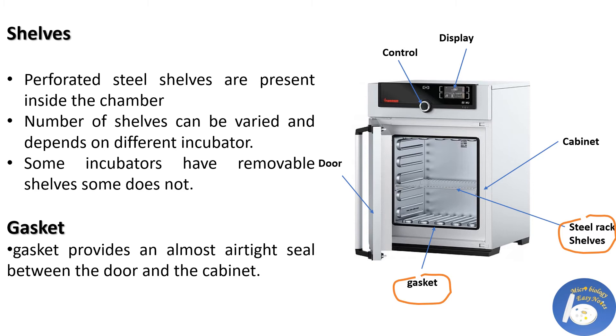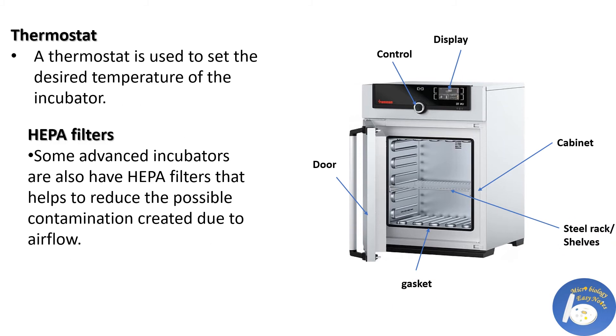The next part is the gasket, which provides an almost airtight seal between the door and the cabinet. This seal prevents outside air from entering the cabinet so the inside hot environment remains undisturbed. The thermostat is used to set the desired temperature of the incubator; after the desired temperature is reached, it automatically maintains that temperature until changed again. Some advanced incubators also have HEPA filters that help reduce possible contamination created due to air flow.